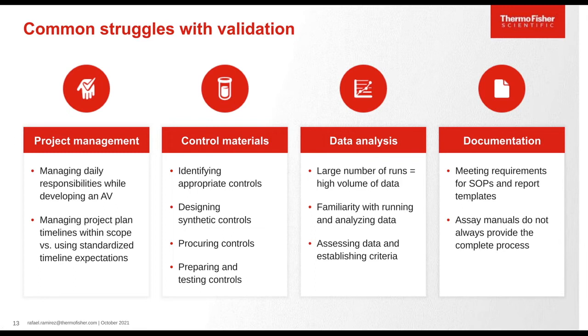Common struggles with validation include: first, project management — managing day-to-day responsibilities while developing a validation takes a lot of time and energy. Second, control material — sourcing and identifying appropriate controls for your panel takes a lot of time, and you may need to design synthetic plasma control materials, then know how to prepare them, make dilutions, and test them in your workflow. Third, data analysis — you could have almost 30 different run files that need to be analyzed and you need to know how to establish your criteria cutoff. Finally, documentation — meeting requirements for SOPs and report templates, as assay manuals don't always go into sufficient detail.